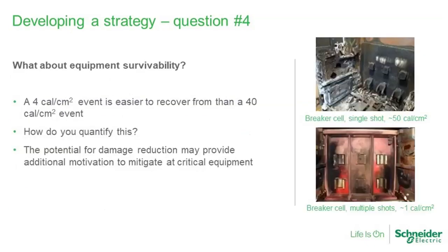Question number 4, what about equipment survivability? This one gets a little bit tricky. We get asked sometimes at Schneider Electric, I want to bring incident energy levels down to help protect against equipment damage. How low do I need to get those incident energy levels before I can be assured that I can re-energize my equipment after it has an arc flash? We don't know. We haven't tested to really figure out what that threshold is. Now, common sense would tell you it's a lot easier to recover from a 4 calorie per centimeter squared event than it is from a 40 calorie event.